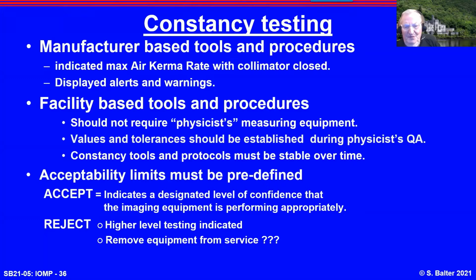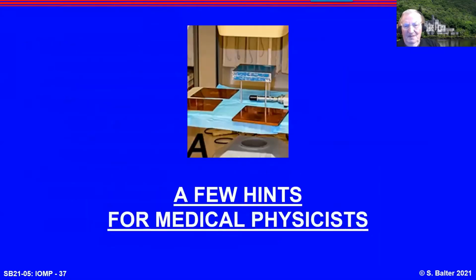Protocols should be stable, a simple tool for output, fixed geometry, put a hunk of plastic in the beam, all the indications, what you expect. You've got to tell the QA team that's doing the constancy what the acceptable values are and a rejection strategy. It might be call the physicist and retest. If it's too far out, you might want the equipment immediately taken out of service. These are professional judgments which you as a physicist need to make.